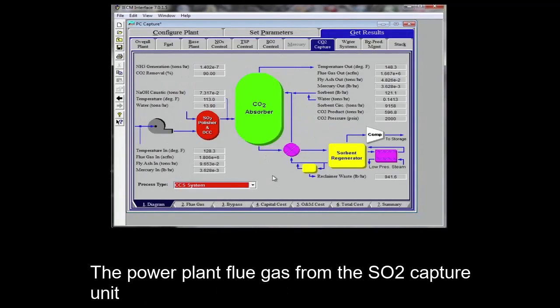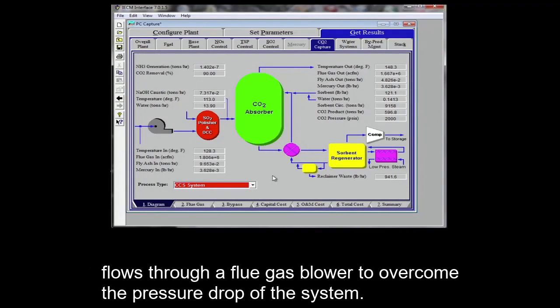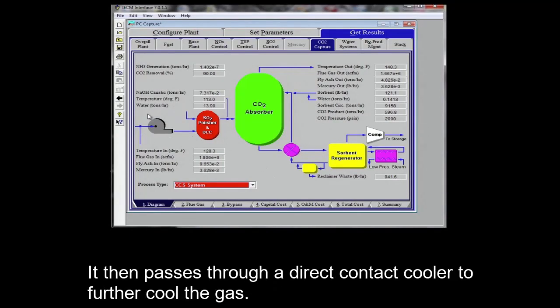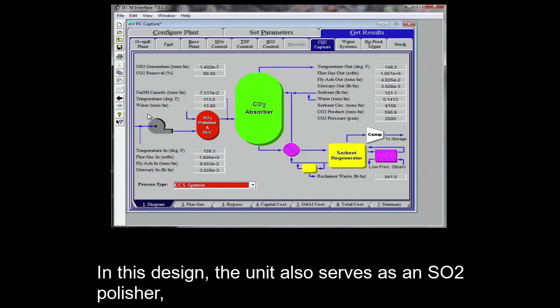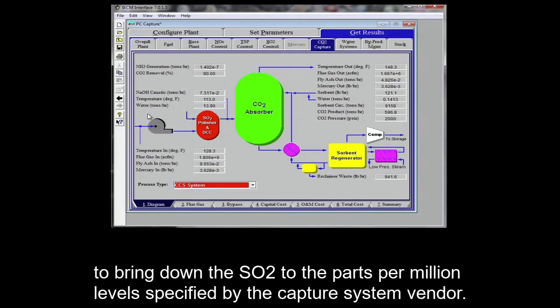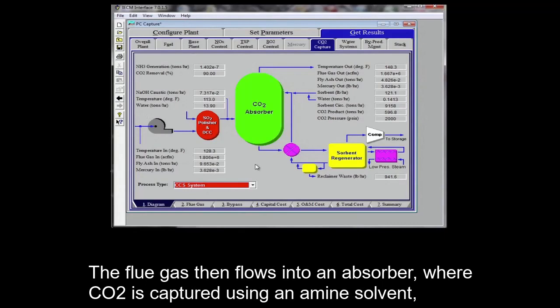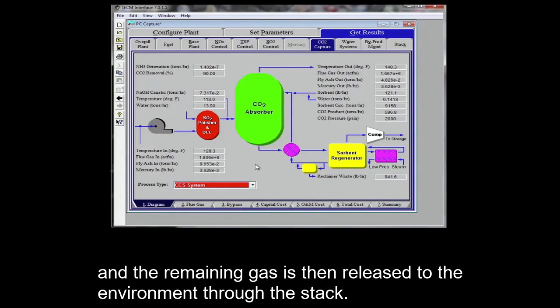The power plant flue gas from the SO2 capture unit flows through a flue gas blower to overcome the pressure drop of the system. It then passes through a direct contact cooler to further cool the gas. In this design, the unit also serves as an SO2 polisher to bring down the SO2 to the parts per million levels specified by the capture system vendor. The flue gas then flows into an absorber where CO2 is captured using an amine solvent and the remaining gas is then released to the environment through the stack.